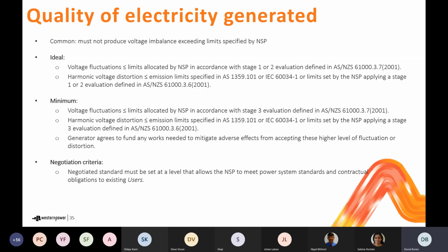The last of the technical requirements considers the quality of the voltage waveform that's being produced by the generating source. The ideal standard is consistent with the requirement in the current technical rules, but that requirement of the current technical rules was really only expressed for synchronous and induction generating units. So it was a little bit silent on what was required for inverter connected generating systems. The requirement's been re-expressed in a way that makes it applicable now for all generating systems.